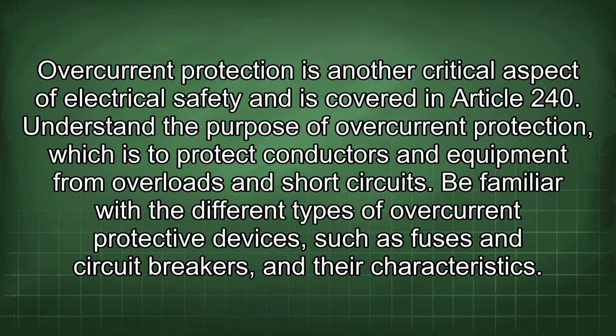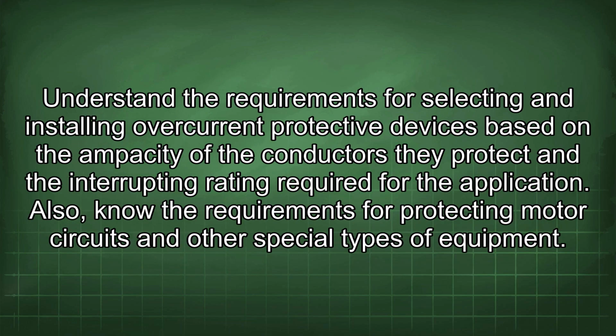Understand the purpose of overcurrent protection, which is to protect conductors and equipment from overloads and short circuits. Be familiar with the different types of overcurrent protective devices, such as fuses and circuit breakers, and their characteristics. Understand the requirements for selecting and installing overcurrent protective devices based on the ampacity of the conductors they protect and the interrupting rating required for the application. Also, know the requirements for protecting motor circuits and other special types of equipment.